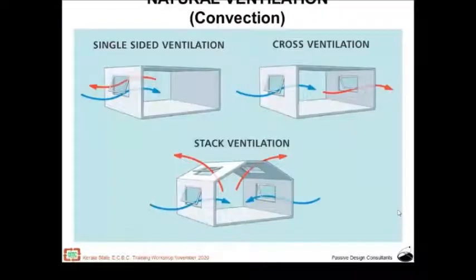When we talk about natural ventilation, we all know about single-sided ventilation, where a room has only a single-side window. So if a building is designed not to be air-conditioned, but with natural ventilation, then there are certain guidelines set by National Building Code 2016. The National Building Code 2016 should be clearly referred to for compliance, even for ECBC, for natural ventilation, where we can have single-sided ventilation or cross ventilation.